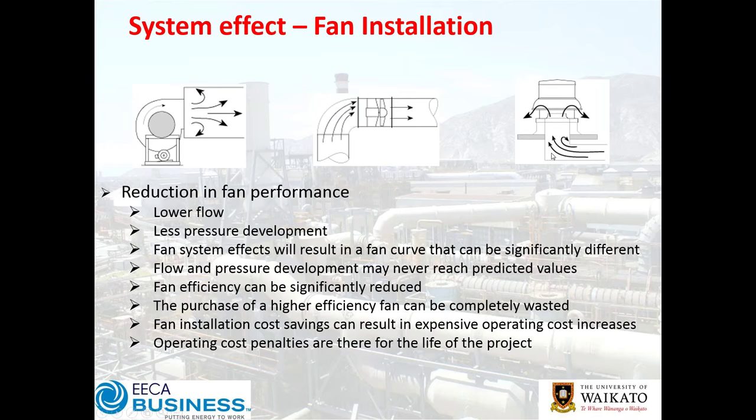On the far right, once again a really poor ducted inlet with additional pressure drop and direct impact on fan performance. Fan installation becomes important in terms of impacting fan performance — it can lower flow and reduce pressure development, moving the fan off its fan curve. Generally these things are detrimental, coming below the fan curve. We were involved with a project a number of years ago where a poor installation resulted in over a 30–40% drop in fan performance, entirely due to the ducting configuration — nothing was wrong with the fan itself, and when corrected, performance was recovered.